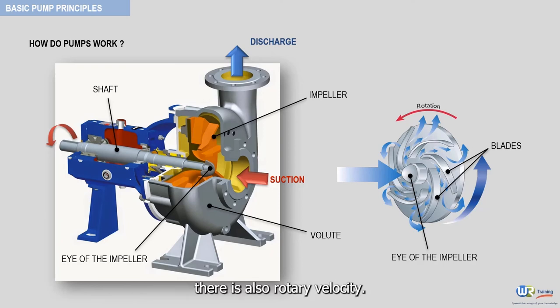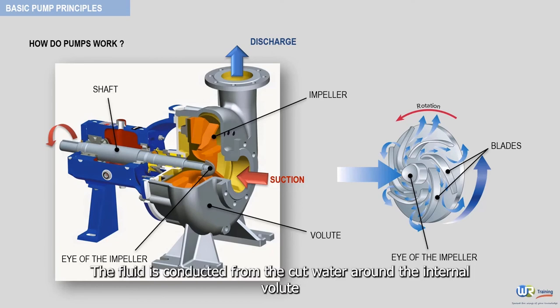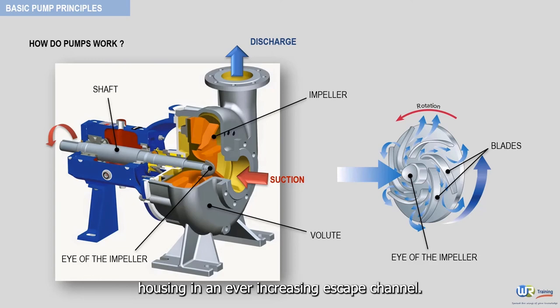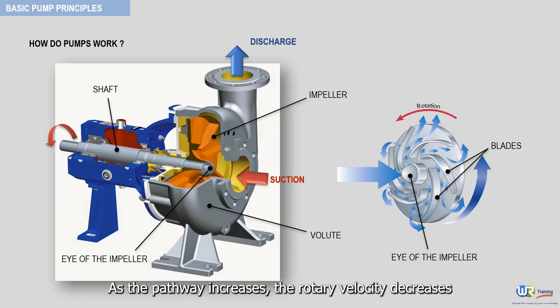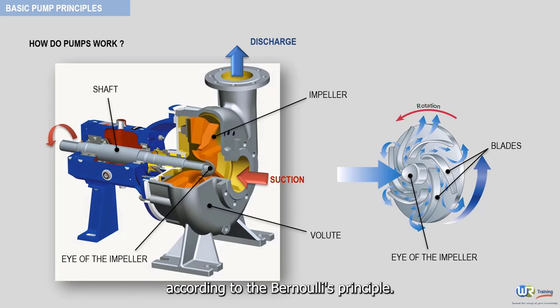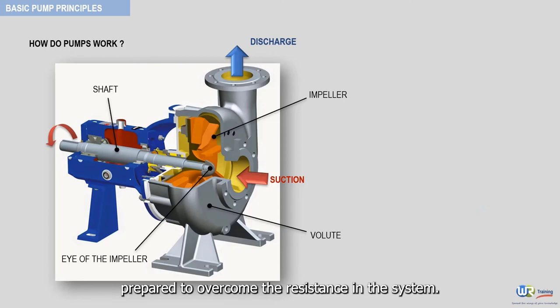This time, according to the reverse of Bernoulli's principle, as velocity goes down, pressure goes up. Because the motor is spinning, there is also rotary velocity. The fluid is conducted from the cutwater around the internal volute housing in an ever-increasing escape channel. As the pathway increases, the rotary velocity decreases, and even more energy and pressure are added to the liquid according to Bernoulli's principle. The liquid leaves the pump at discharge pressure, prepared to overcome the resistance in the system.